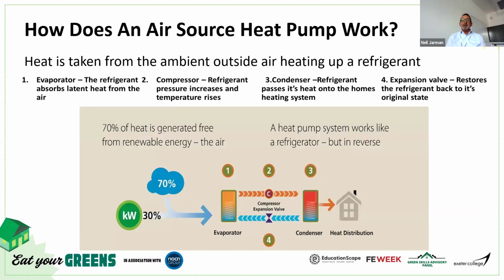So the dynamics and how it works. The numbers you can see there, 1 to 4, are all located inside that outdoor unit. In effect, that outdoor unit, the air source heat pump, is almost like a boiler sited outdoors. You've got 28mm flow and return connections to the back of that unit, and that unit will supply your cylinder and your heating system, hot water, in the same way a boiler would.